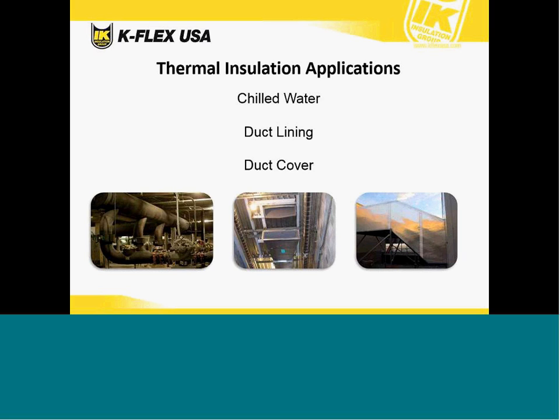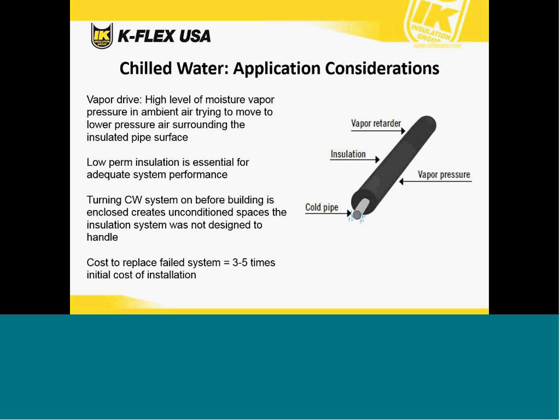We're going to discuss some thermal insulation applications. We'll start with chilled water applications. Some application considerations for chilled water systems. The big one here is the vapor drive. The chilled water pipe has what we call vapor drive. It's a high level of moisture vapor pressure in ambient air trying to move to the low pressure air surrounding the insulated pipe surface. And now an insulation system will prevent the moisture vapor from hitting the surface and condensing. Insulation is essential for adequate system performance.